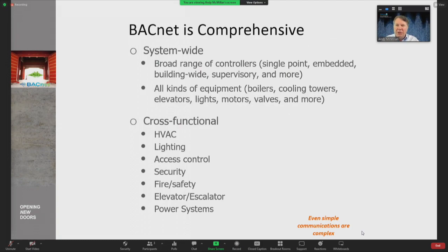Another dimension in which BACnet is comprehensive is functionality - the specific functionality of BACnet to deal with lighting, because lighting has certain attributes that need that. The same with access control, intrinsic security, fire safety, elevators and escalators, HVAC, and power systems. So BACnet has messages, actions, and responses designed specifically for all of these different sub-functions in a building.